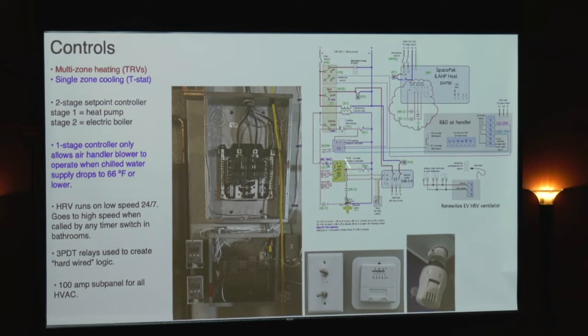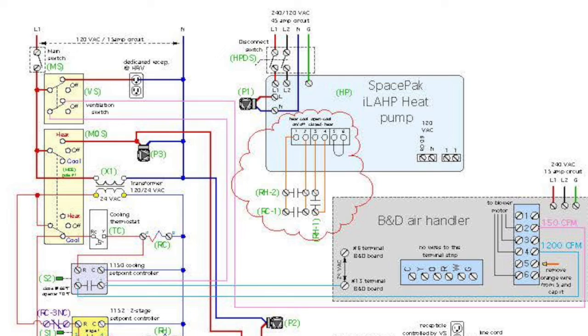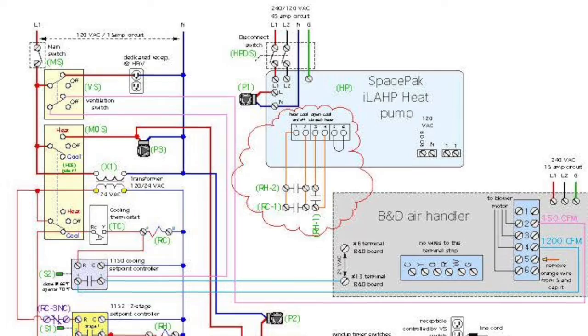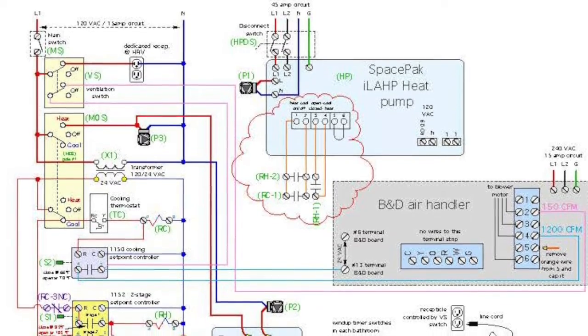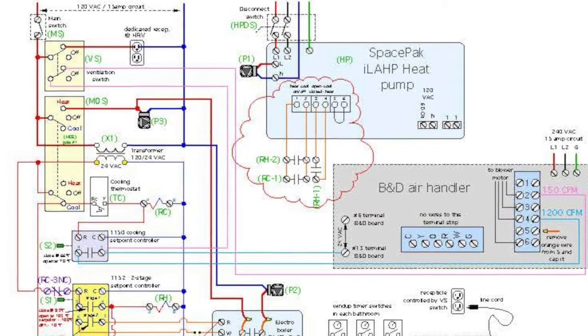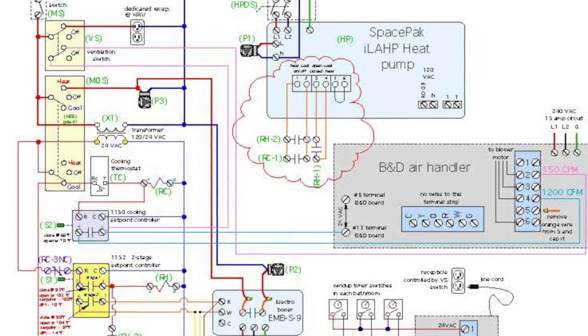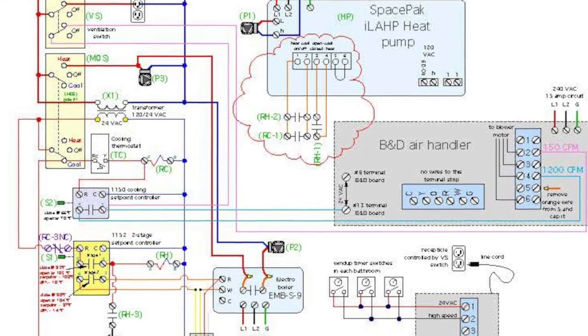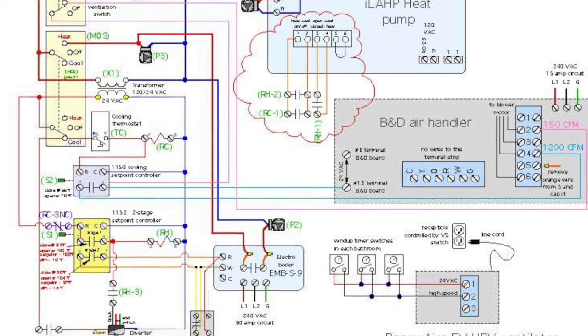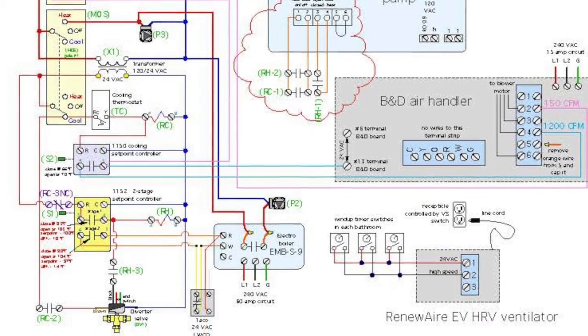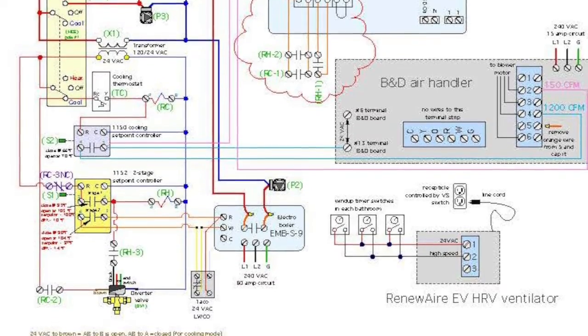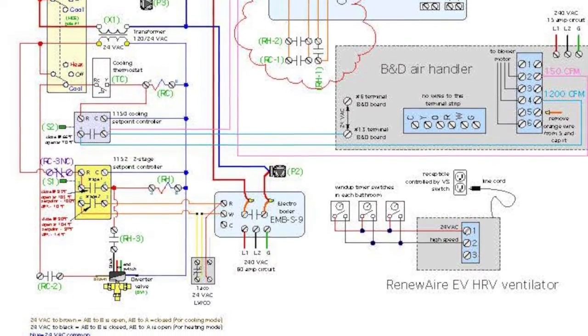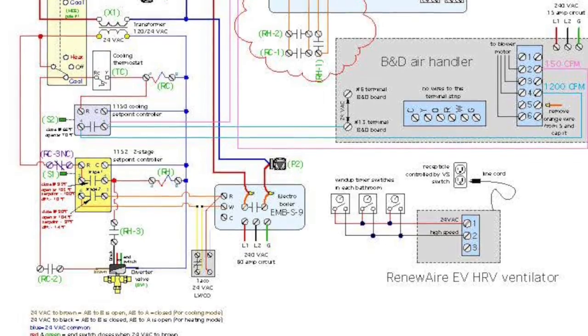And again, I'll make the slides available as PDFs. It looks complicated, but really it's a bunch of switches. There's basically one switch that sets the mode of the system. It's either heat, off, or cool. It's just a toggle switch with a center off position, okay? And then that switch basically interacts with other devices, a couple relays, triple pole, double throw relays, industrial relays. Again, you can buy them very easily. And we created the logic to operate this system using what I call hardwired logic.